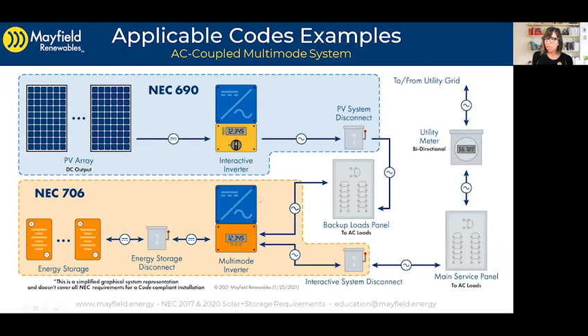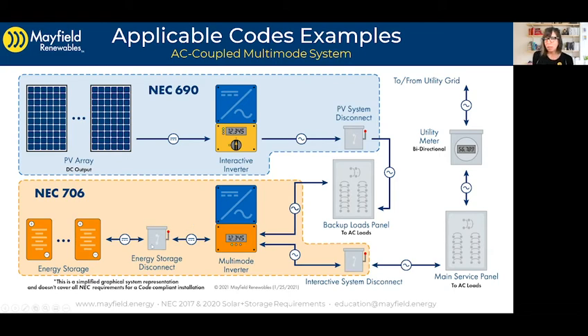Things like product listing to UL 9540 and 9540A — that's going to apply to the energy storage system, energy storage disconnect, and multimode inverter. All those listing requirements we have to think about on these pieces of equipment. And then when we get into disconnecting means and installation requirements such as working space, all of those different sections that we talked about now have to be applied to this exact system.